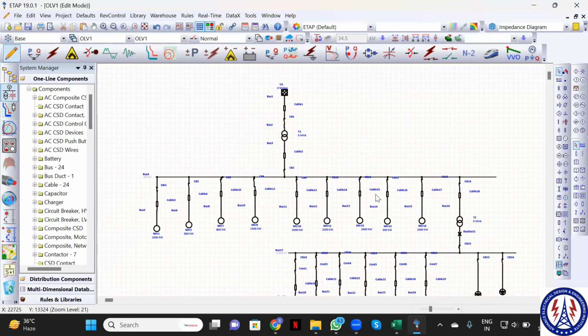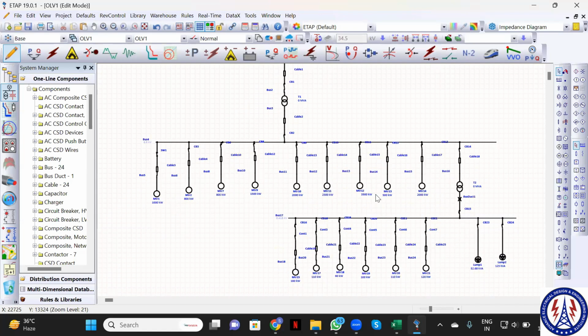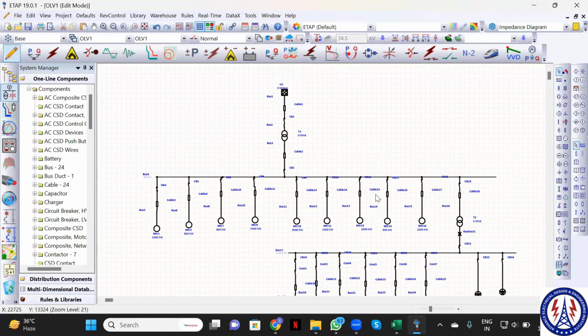So we have provided the rating for everything, right? You can see various cables are there, right? I am giving you one exercise. You have to size one LV cable and one HT cable, and that data we will put in ETAP. Remember, ETAP provides an error only when your cable is undersized. We can also size the cable with the help of ETAP, but right now I want you to do it manually. When we go further, I will tell you how to model this.